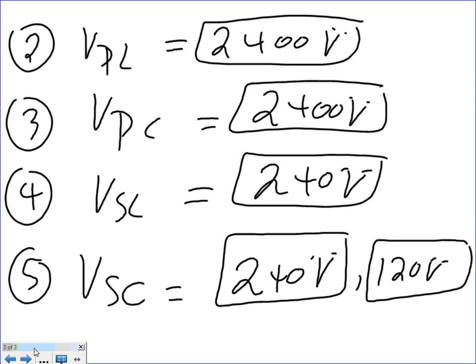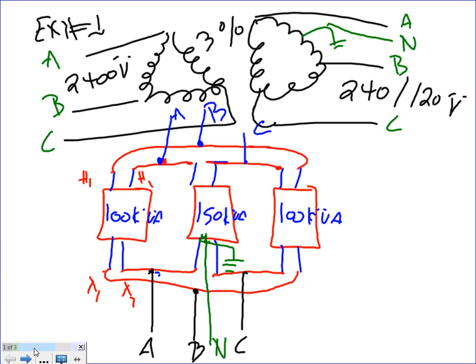Yes, sir, the one where you found the single phase KVA, using the 100, what if there were three different values? Give me a scenario. Like if a bank was 75 KVA, one was 100, one was 150. You would never do that, guys. Here's how we bank it, and I'll tell you why. What if that was 75, this was 150, and this was 100? You would never do that. It's always two transformers the same, and the third one bigger, because that one is going to see the single phase. So they always put two transformers the same size, and the third one bigger, and the biggest one is always the one that has a neutral.